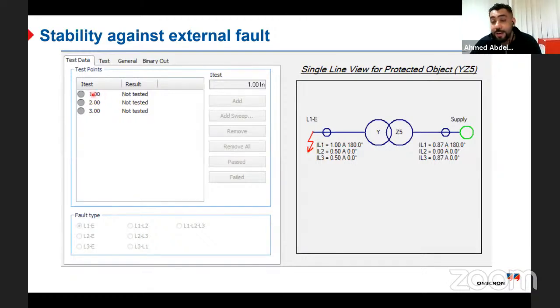So for example, here, if I inject 1 per unit as a bias current, the second will be 2 per unit, 3 per unit, and the differential current will be 0. Afterward, I will say that my system is completely stable. There is nothing wrong, because maybe you will have a wiring issue. Maybe your protection relay is fine, but with the wiring, while the commissioning engineer is doing some kind of modification, he just swapped two phases, red instead of yellow, yellow instead of blue.